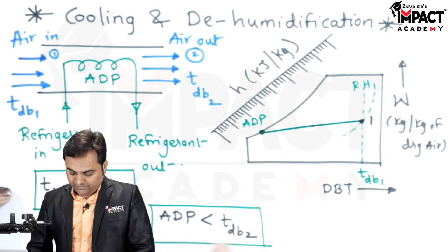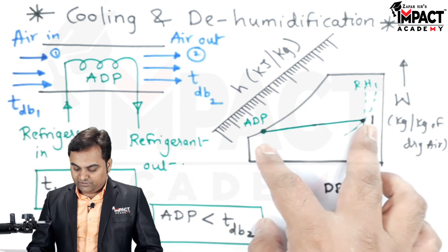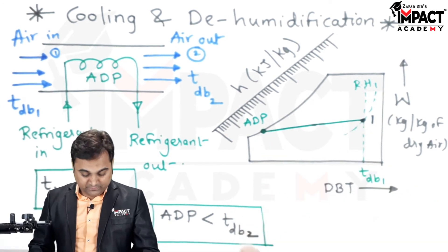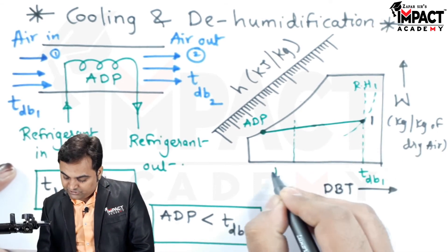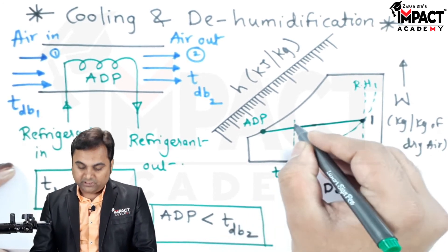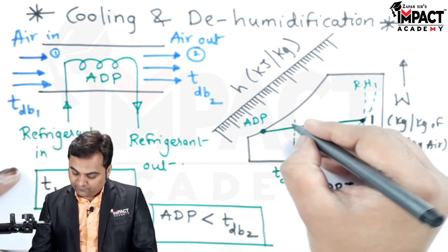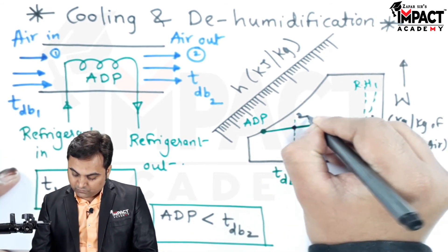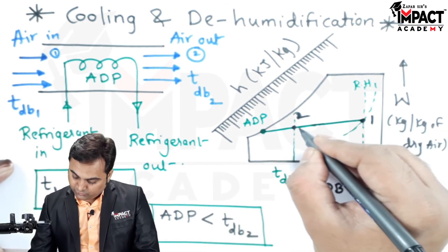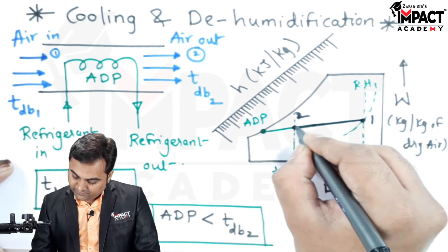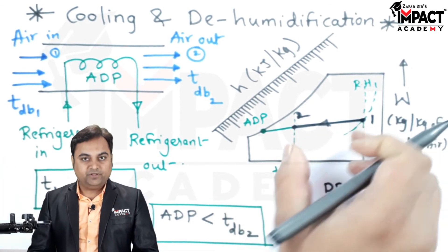The apparatus dew point temperature is less than the exit dry bulb temperature of the air, so the exit dry bulb temperature should lie on this line. Plotting the exit dry bulb temperature upward, where it intersects this line gives us point number two, which is the dry bulb temperature of the exit air. Joining point one and point two indicates the process, which is called the cooling and dehumidification process.